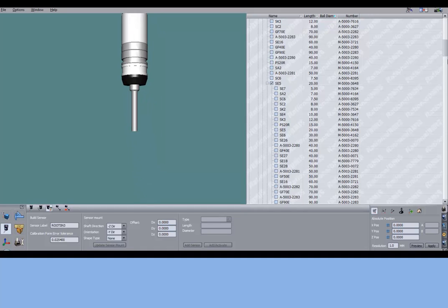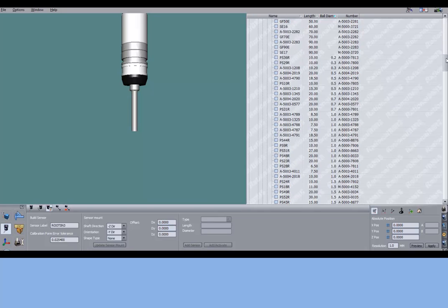And next, if you have a probe attached down after this extension, this is where you're looking for a probe. Because you already sorted the ball diameter in ascending order, the easiest way is to look at the ball diameter column, and let's say I have a 2mm by 20, which is very typical for a lot of CMM users. So I click on it.